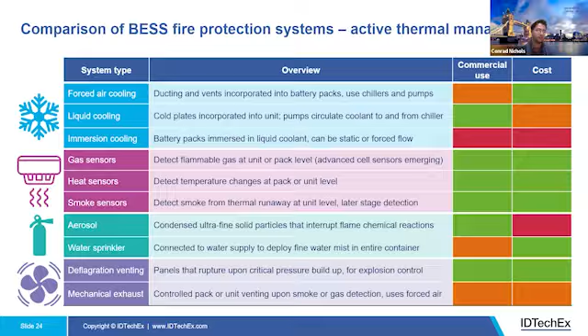And finally, deflagration venting. This is a key safety measure in BESS, and it's designed to safely release pressure from the building up of off-gases and any flames during a thermal runaway event. It doesn't prevent failures. Venting helps limit damage when integrated as part of a broader fire and thermal management strategy. Passive vents remain the most widely used option due to their cost effectiveness, but you can also have active vents which are triggered in a different way. And you have systems that might combine both active and passive venting for greater responsiveness and venting control while balancing cost at the same time.